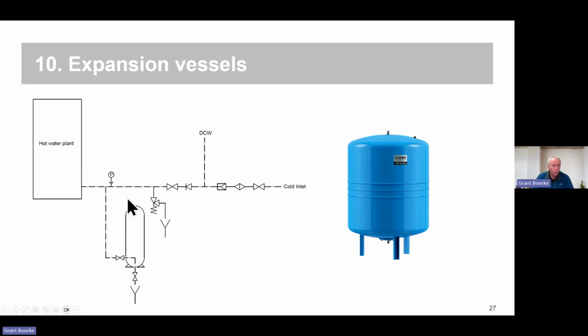Once you've got this pressurized to the system pressure, you can open the system, bleed all the air out of it, and then once you've bled all the air out, shut it off, and away it goes. Once you've done that, you want to heat the system fully from cold to hot, and check that you haven't got anything coming out of the expansion control valve or the TPR valve, and that the pressure of the system's about right.